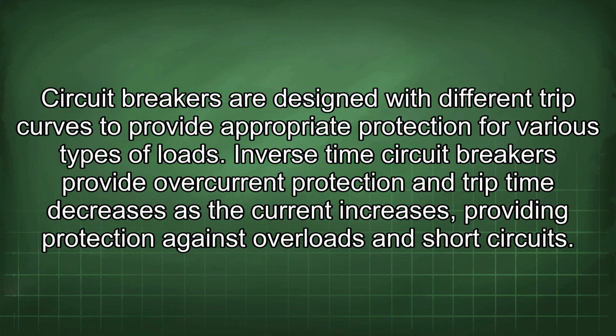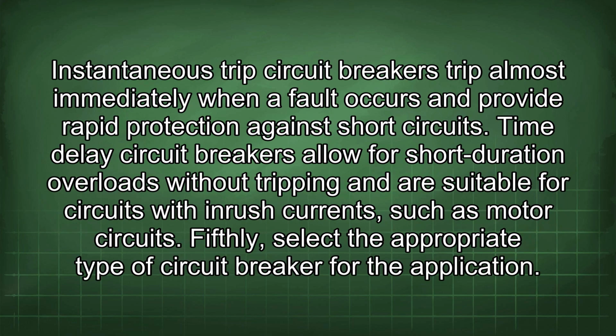Circuit breakers are designed with different trip curves to provide appropriate protection for various types of loads. Inverse time circuit breakers provide overcurrent protection, and trip time decreases as the current increases, providing protection against overloads and short circuits. Instantaneous trip circuit breakers trip almost immediately when a fault occurs and provide rapid protection against short circuits. Time delay circuit breakers allow for short duration overloads without tripping and are suitable for circuits with inrush currents such as motor circuits. Fifthly, select the appropriate type of circuit breaker for the application.